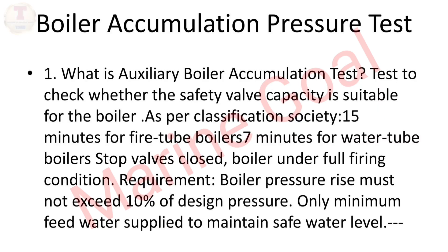Boiler accumulation pressure test. What is the auxiliary boiler accumulation test? It is a test to check whether the safety valve capacity is suitable for the boiler. As per classification society requirements: 15 minutes for fire tube boilers, 7 minutes for water tube boilers.